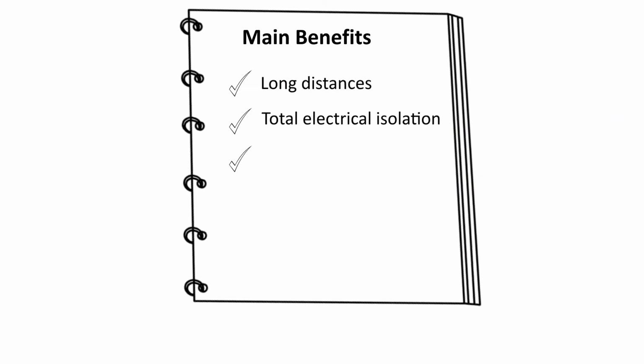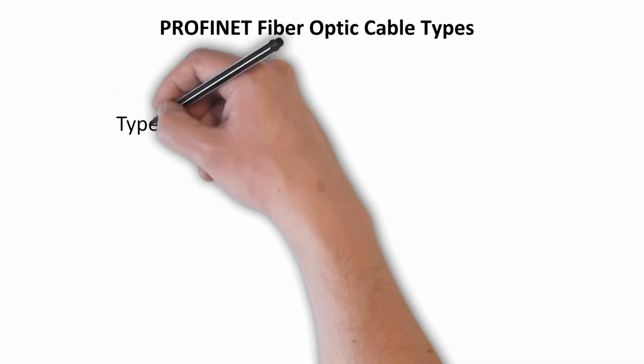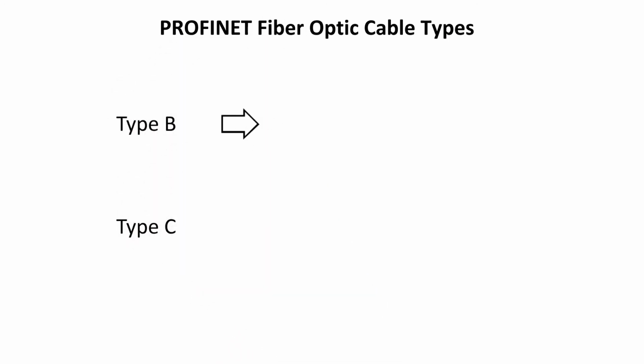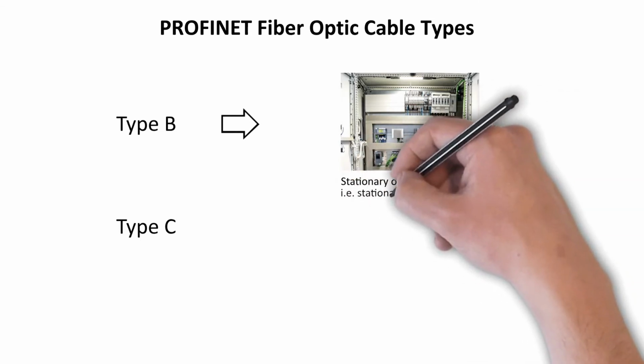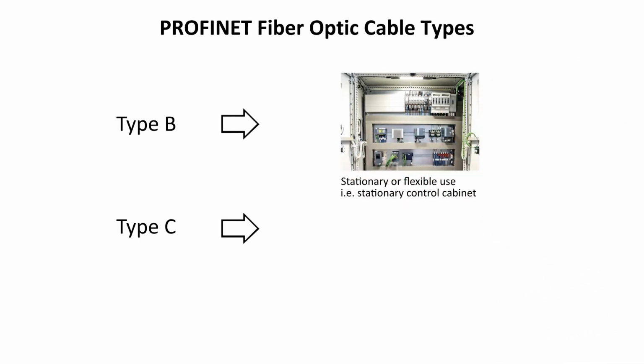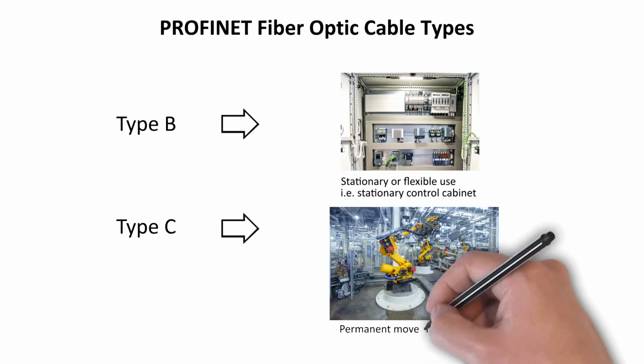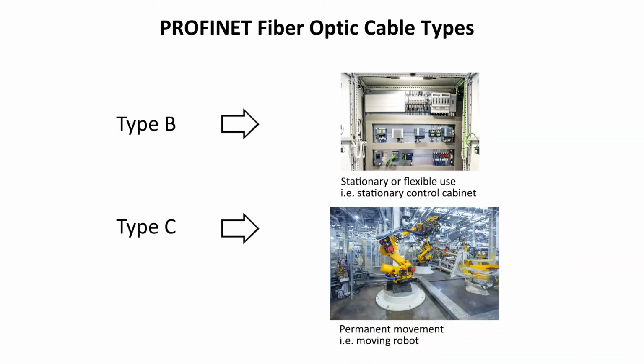Fiber cables offer benefits in very specific instances. They can cover distances of kilometers, and they provide total electrical isolation between plant areas. Also, fiber cables are immune to electromagnetic interference. There are two Profinet fiber optic cable types, Type B and Type C. Type B cables are meant for stationary or flexible use. Type C cables are designed for special applications like, for example, permanent movement, vibration, or torsion.